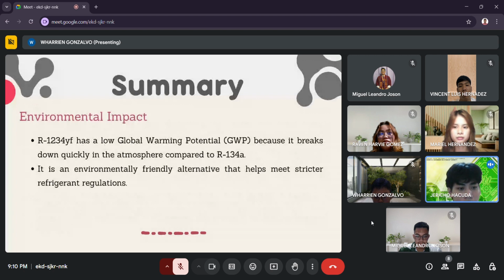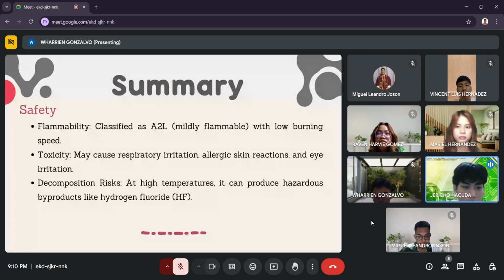On the environmental impact, R1234yf has a low global warming potential, or GWP, because it breaks down quickly in the atmosphere compared to R134a. It is an environmentally friendly alternative that helps meet stricter refrigerant regulations. And for the safety, the flammability is classified as A2L, or mildly flammable with low burning speed. Toxicity: it may cause respiratory irritation, allergic skin reaction, and eye irritation. Decomposition risk: at high temperatures, it can produce hazardous byproducts like hydrogen fluoride.